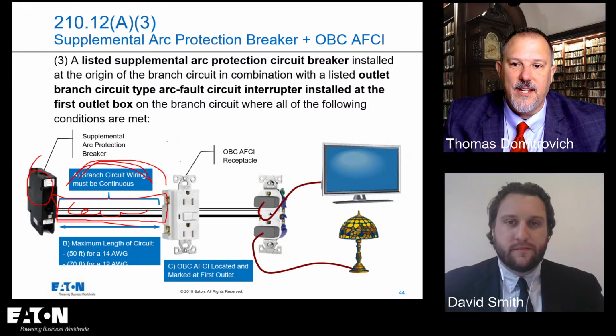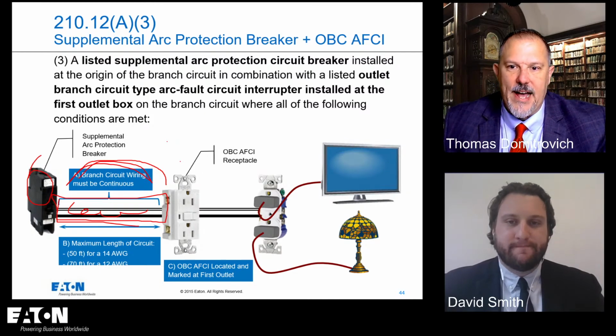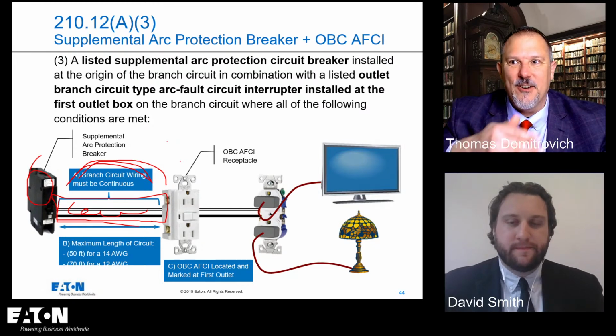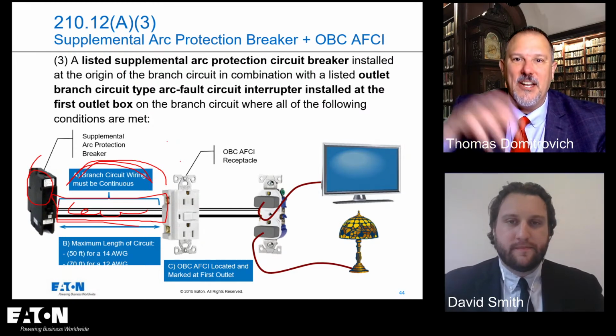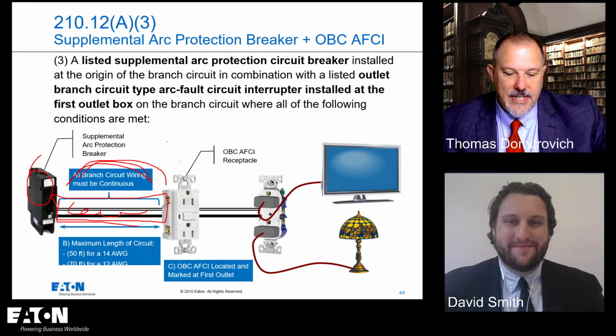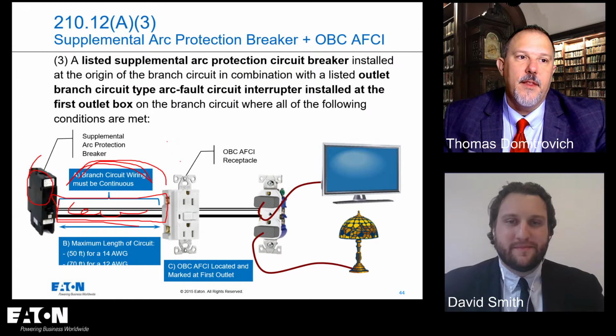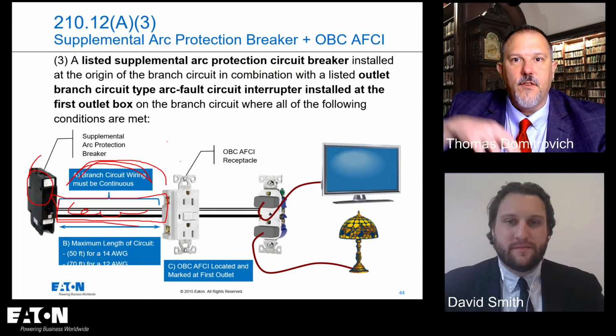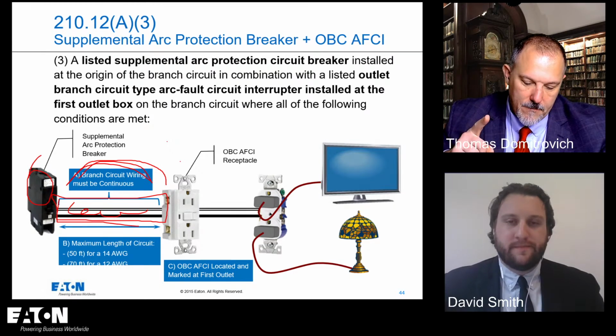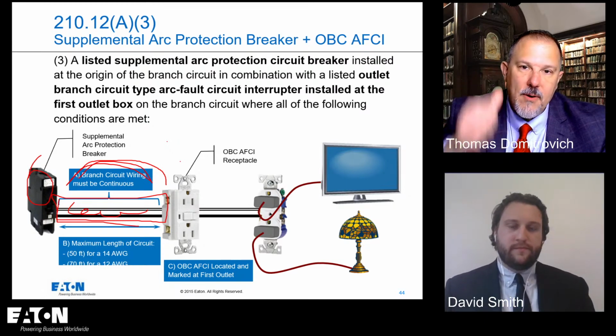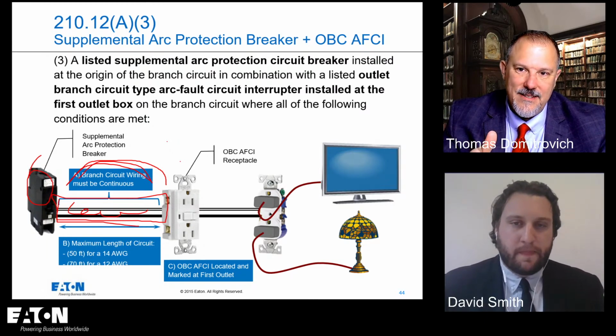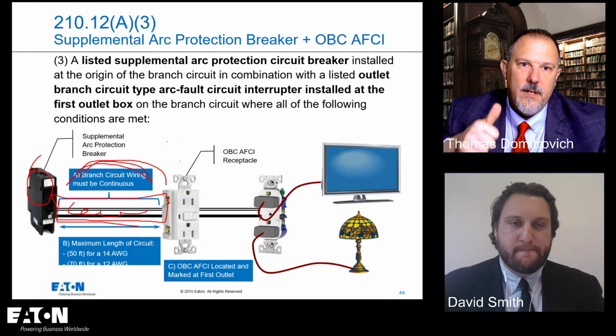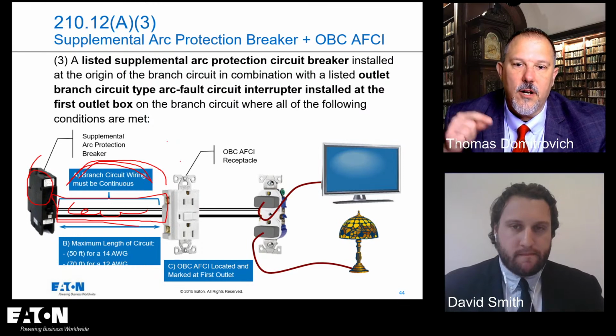You've got a public input. You've got to get a report out really fast. Actually, it was trying to get a report out for the public input phase. He got it out. Panel 2, we looked at it and we said, hey, you've got to tweak this. So they worked on it for the public comment phase. Now, the problem with the instantaneous was that UL 489 does not require an instantaneous on a molded case circuit breaker.